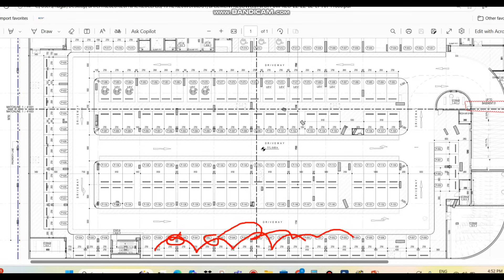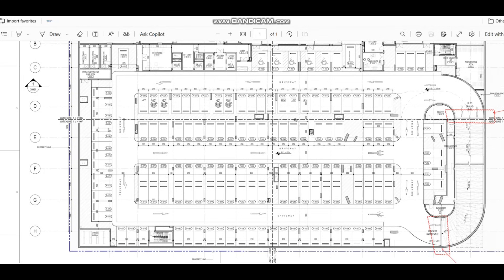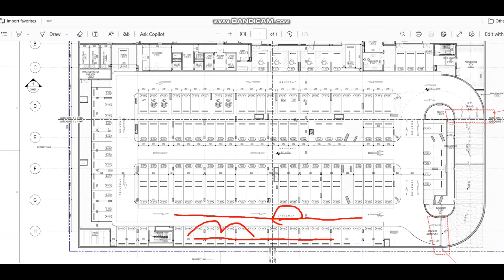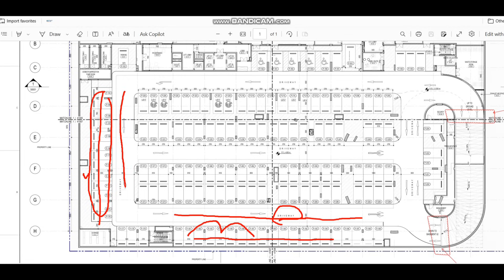To summarize exhaust and fresh air grill placement: place exhaust grills over the parking spaces following the uniform method (every two to three cars), and place the fresh air supply grills above the driveway areas. This arrangement ensures proper cross-ventilation and air circulation throughout the car park.